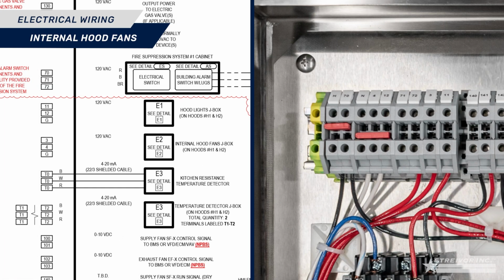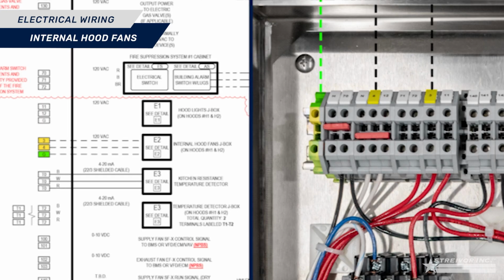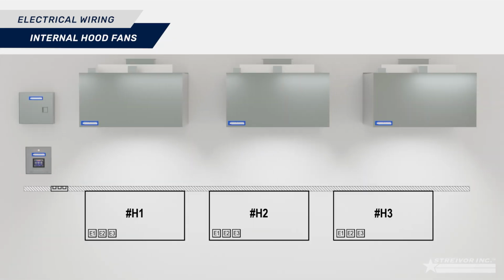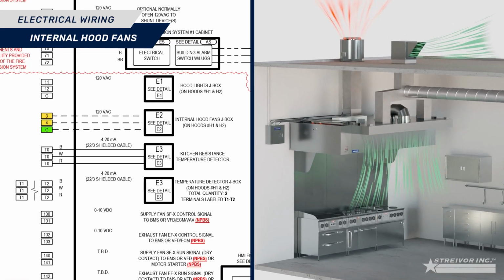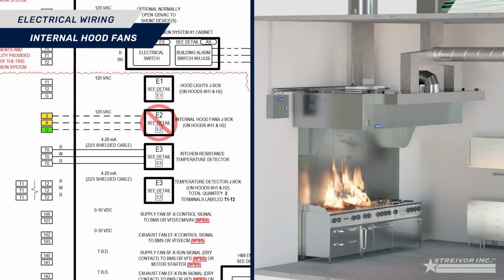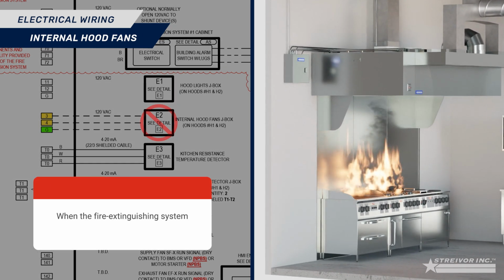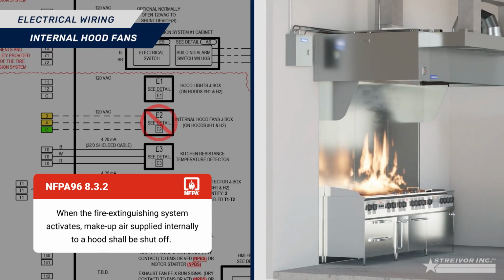To supply power to your internal hood fans, IHF, if applicable, wire terminal block 3 hot, terminal block 4 neutral, and ground in the control panel to the wires in the junction box labeled E2 on the hood. If the control panel is controlling the IHF on multiple hoods, locate the E2 junction boxes for each additional hood and daisy chain them together. Internal hood fan power to terminal blocks 3 and 4 will be automatically shunt during a fire suppression system activation to comply with NFPA 96 Section 8.3.2.